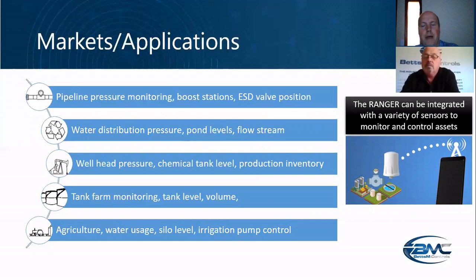And because you know my bias towards VTScada, you said you also had set that up? Yes, we actually have an application where the MQTT device talks to a T-Box RTU acting as a broker, and that broker interfaces via cell to the Ranger and by Ethernet to VTScada. Then we have a protocol converter inside VTScada to convert the data from Sparkplug B to OPC data.